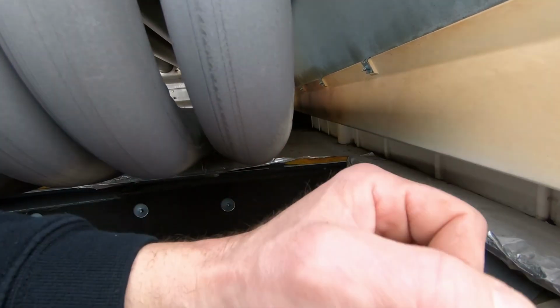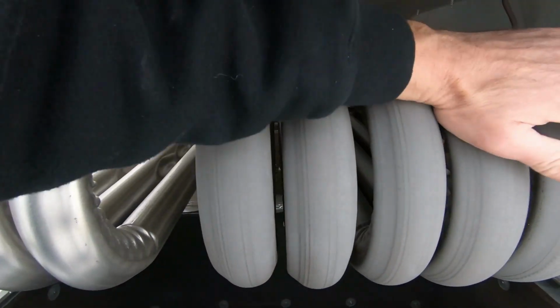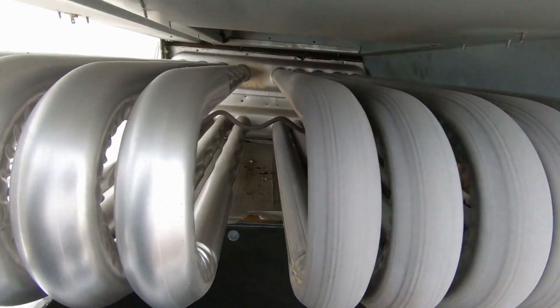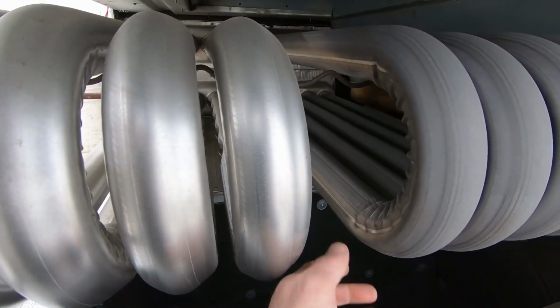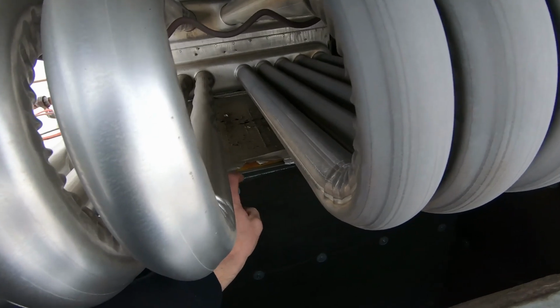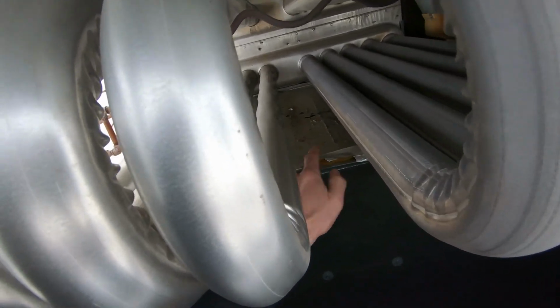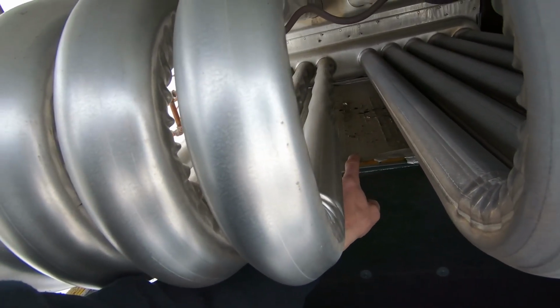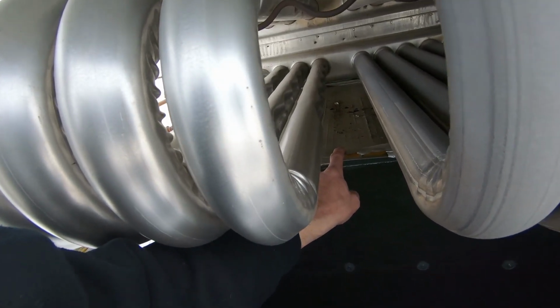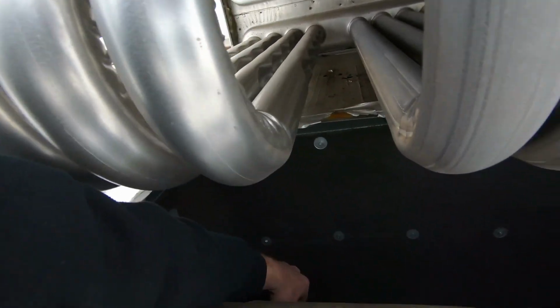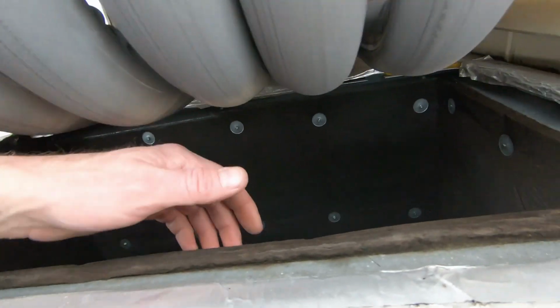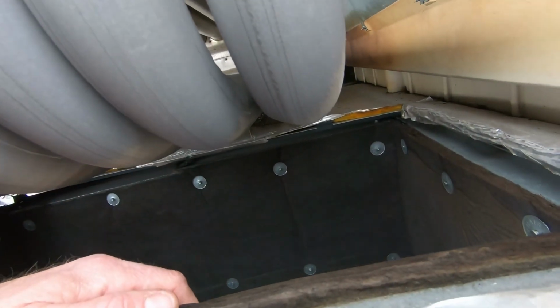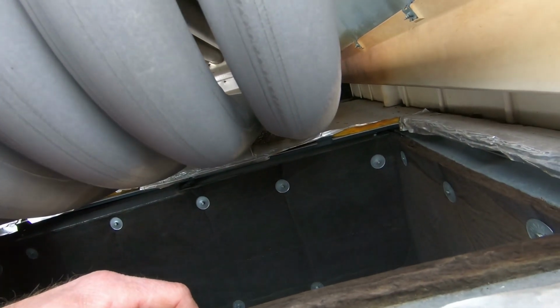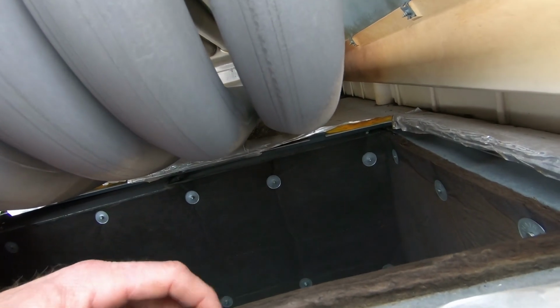That's plastic. It melted the filters. It melted numerous wires. I'm shocked that this heat exchanger isn't cracked. That's why I gave it a second look. Insulation down, fiberglass insulation on the base of the unit, it is brittle. It's dry. Somebody got real lucky here today, or yesterday, or whenever this call came in.